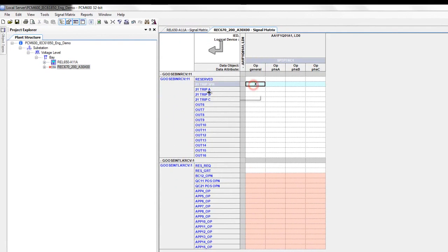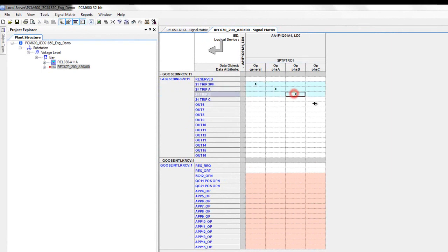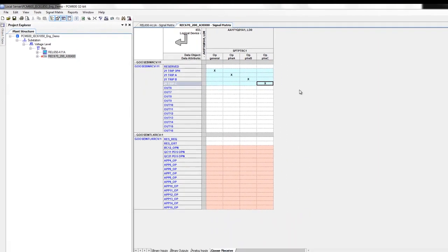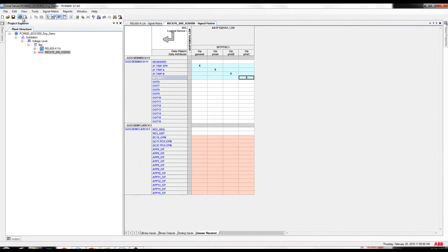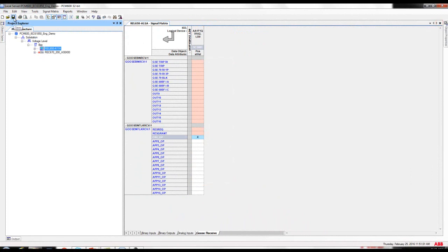Map the signals — I configure it in such a way that I expect to receive all of them and do something with these signals. Once you have done the changes, click save and close the tool. Click save and close the tool. Now both ABB relays, the REL650 and REC670, are completely configured to send and receive GOOSE messages on the station bus.